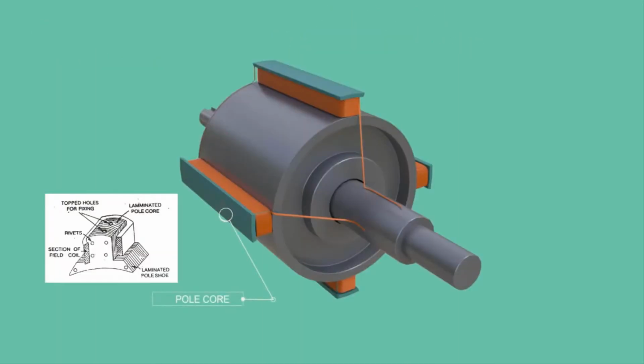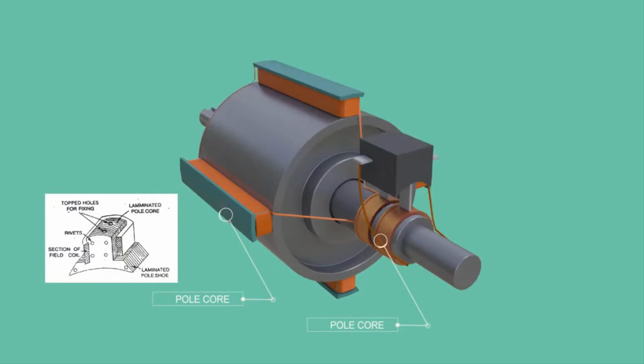Pole core is used to effectively transfer magnetic flux, and they are made with fairly thick steel lamina. Such insulated lamina reduces energy loss due to eddy current formation. DC current is supplied to the rotor with a pair of slip rings. This is the reason why a rotating magnetic field approach is used in the alternator.